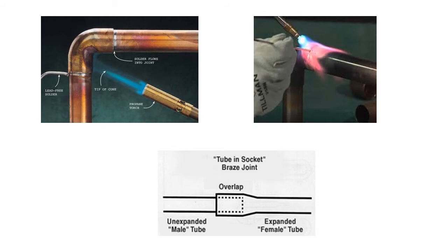The basic difference between soldering and brazing is the temperature necessary to melt the filler metal. The temperature is defined to be 842 degrees by the American Welding Society, but often it is rounded off to 840. If the filler metal melts below 840, the process being performed is soldering. Above that temperature, the process is brazing. The melting point of copper is 1,984 degrees Fahrenheit. As such, the filler metals for soldering and brazing copper and fittings must have melting temperatures below this temperature.